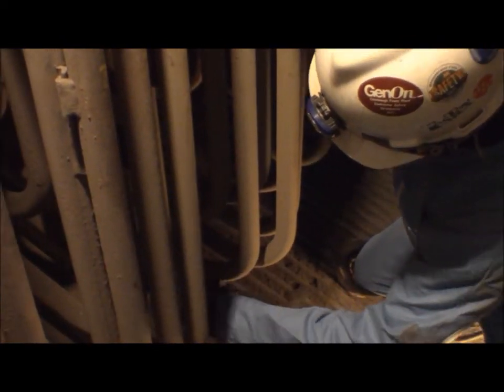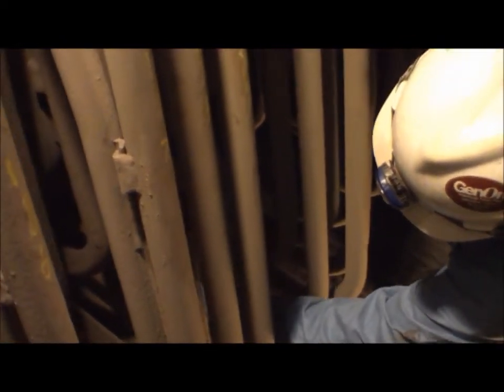Here the technician is scanning the tube. He starts approximately one foot above the bend and scans through the bend. If there is any indication of magnetite, the technician re-scans the tube and marks the specific location of magnetite.